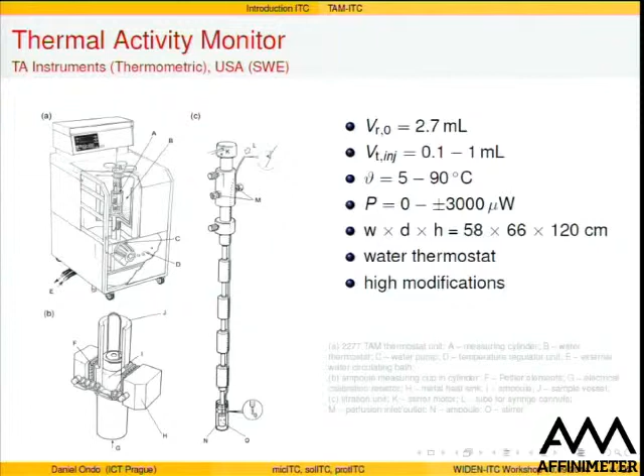Shortly, here is one of the calorimeters which I'm used to working with. It's the thermal activity monitor developed in Sweden, but now sold by Thermal Analysis Instruments. It's quite old nowadays and not used very often because it has a high time constant. But it's a modular calorimeter where the titration cell is placed into the heat conduction channel. It works from 5 to 90 degrees Celsius. We can vary the reaction volume and also the injection volume. The thermostatization is done by a water thermostat.